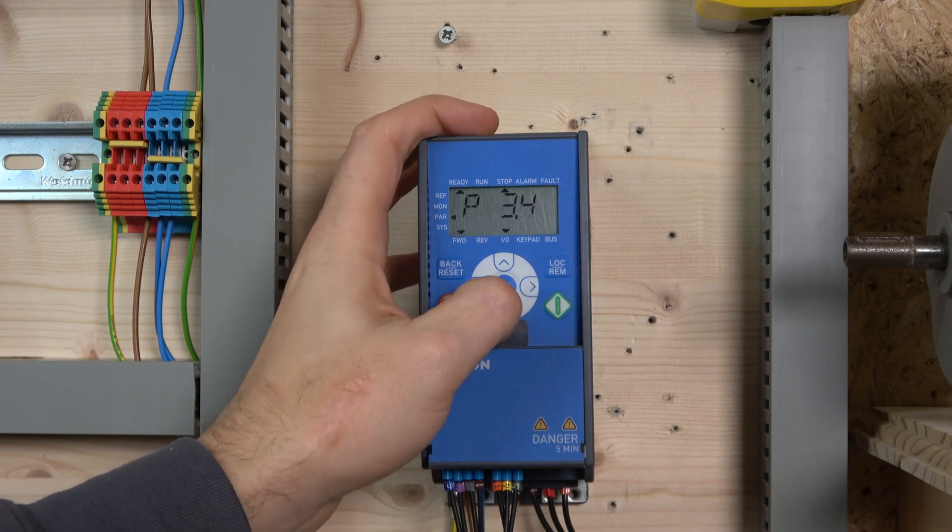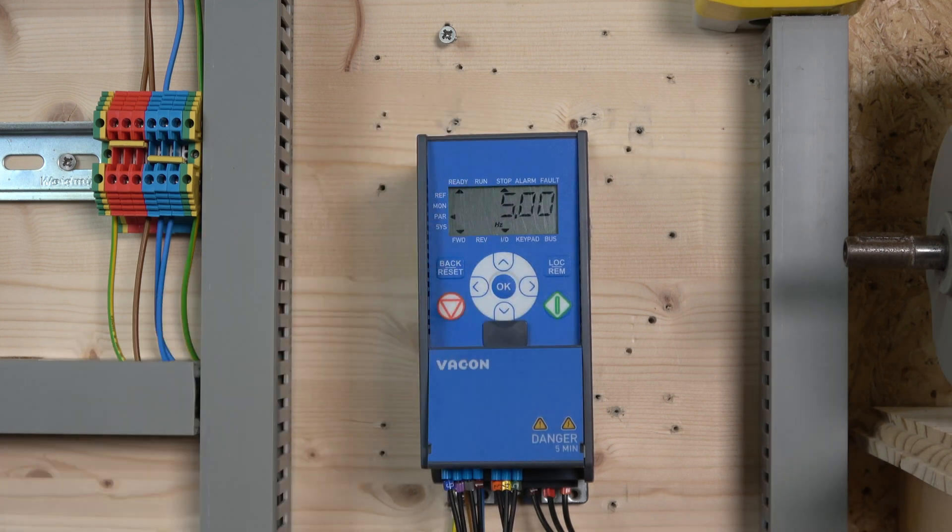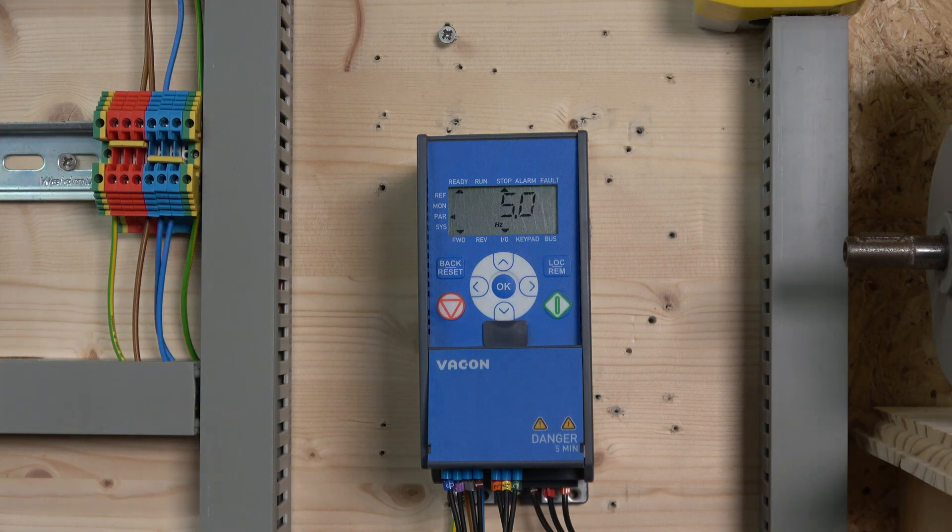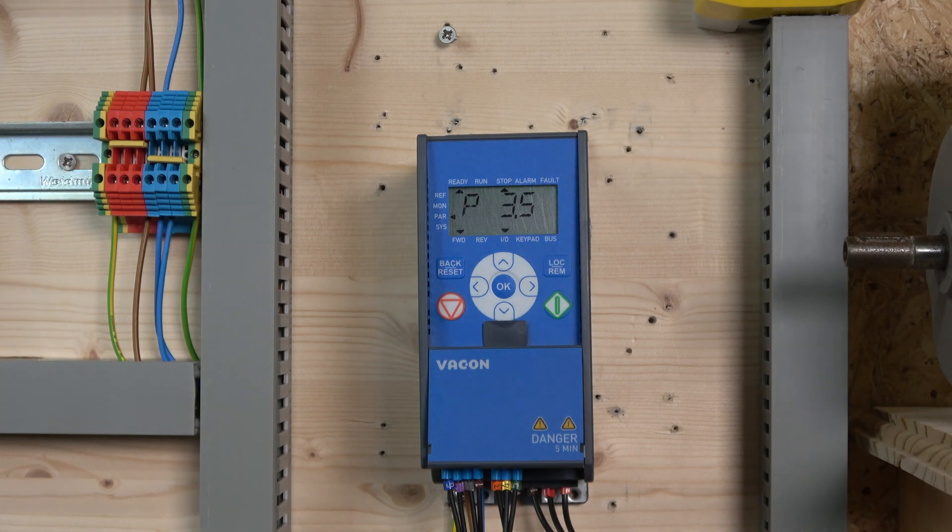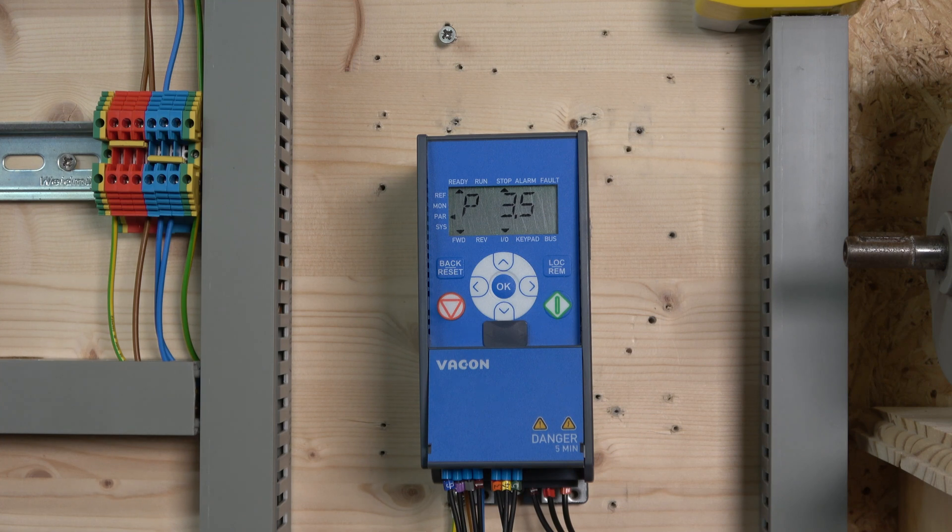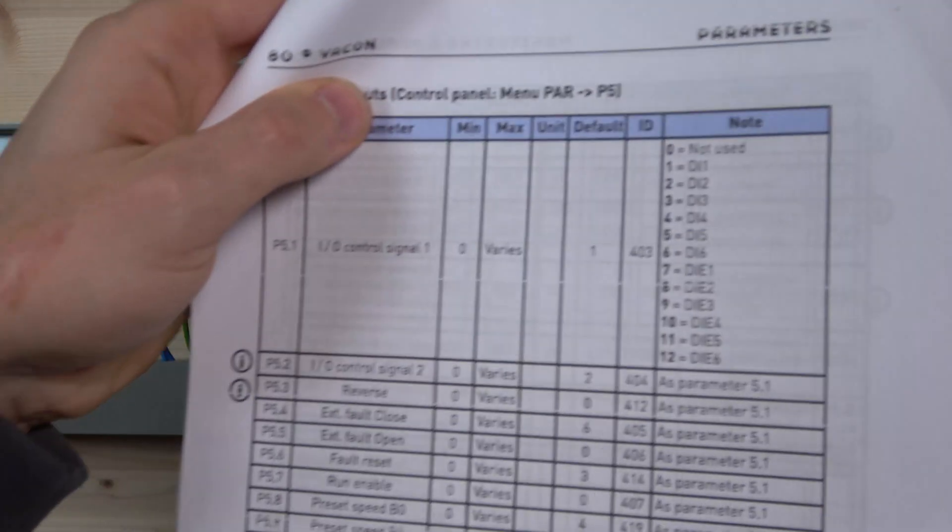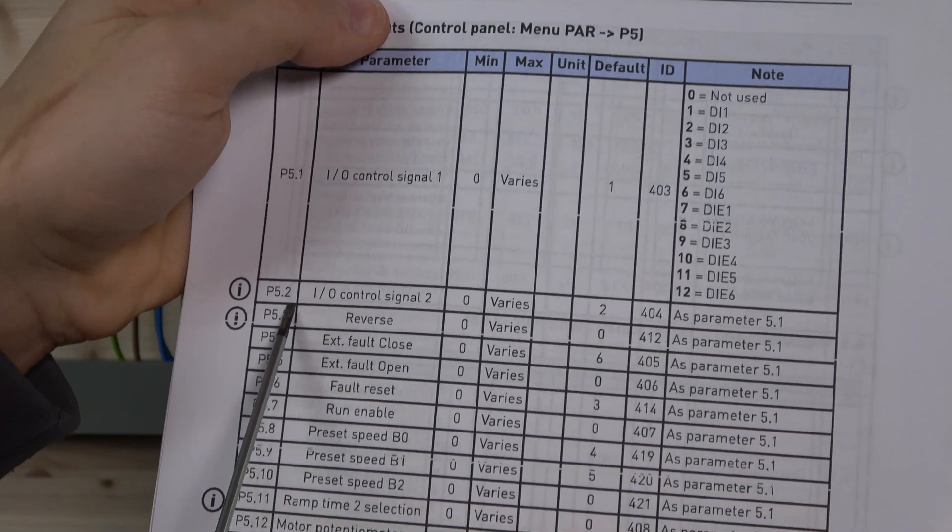In parameter 3.5, I changed it to 5 Hertz, which will give me a preset frequency. In our case, we'll call it jog. I didn't use the default because I want to show you how to reprogram your I/Os. In this drive, same as others, you have to select what you're trying to achieve.